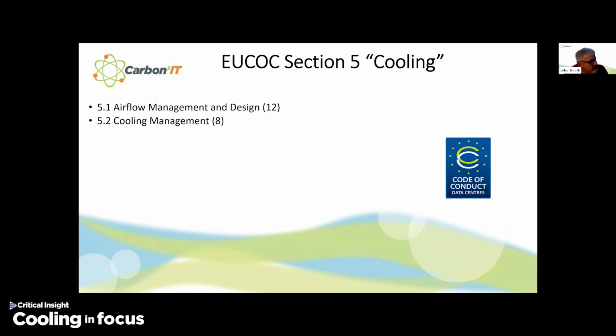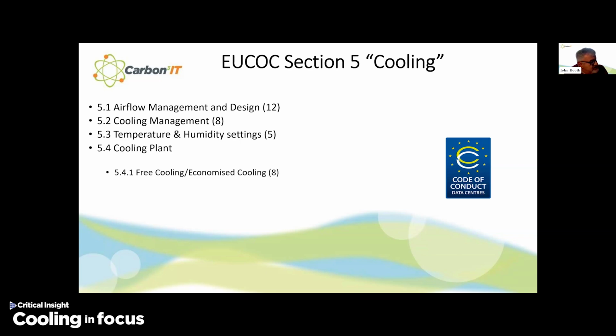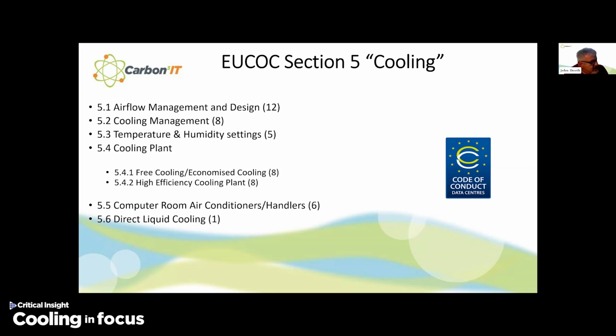So just to cover, we've got 12 practices in airflow management and design, 8 in cooling management, 5 in temperature and humidity settings, cooling plant, 8 in free cooling, 8 in high efficiency cooling plant, 6 for computer room air handlers, 1 for direct liquid cooling, 5 for data center waste heat. In total, 53 best practices. That's almost a third of the code of conduct. So you can see that it's considered to be quite important.